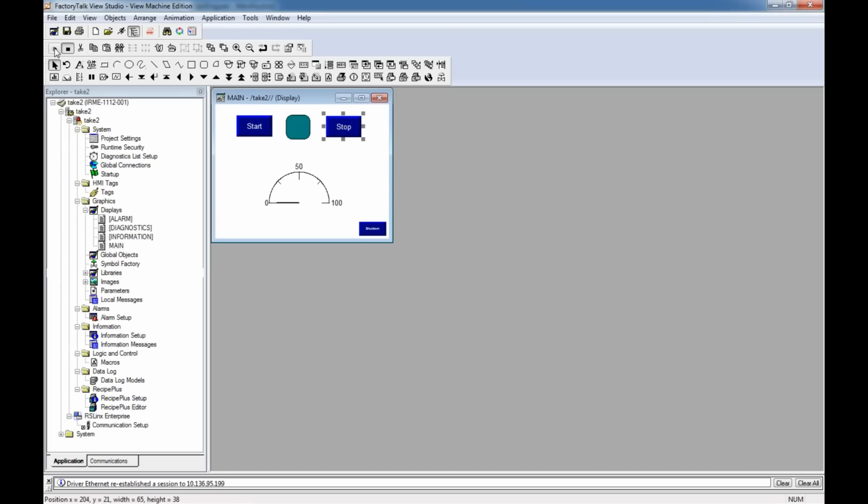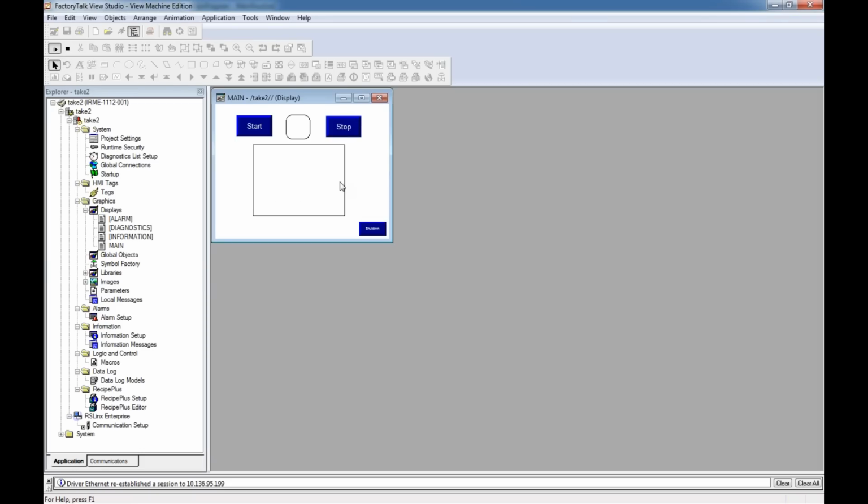If I want to test this, I go up here and hit the play button, and let's see if it'll let me start. I just clicked it, and I heard my thing click. There it is, it's starting. And you can see it's accelerating. I might have to adjust the scale a little bit because it's going too much. And you can see now it's at reference.